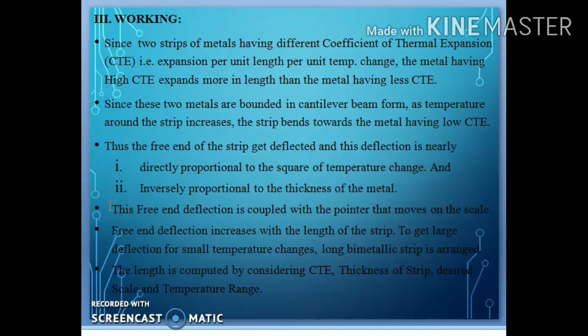The working substance that can be used in a bimetallic thermometer is usually Invar. Invar is usually employed as the metal with low coefficient of thermal expansion. Its temperature coefficient of expansion is around 1/20th of ordinary metals. As the high expansion metal, brass can be used at lower temperatures, and nickel alloys can be used for higher temperature applications. The metal used in the bimetallic strip is usually the low expansion metal Invar. Invar is an alloy of 64% iron and 36% nickel, and as the high expansion metal we generally use brass, nickel, and nickel molybdenum alloys.